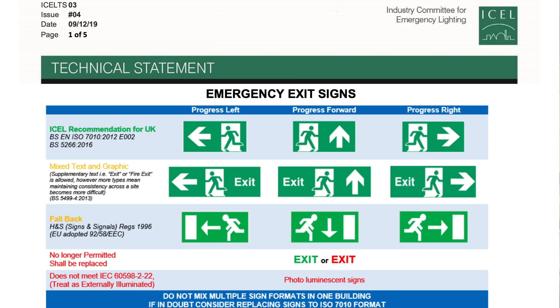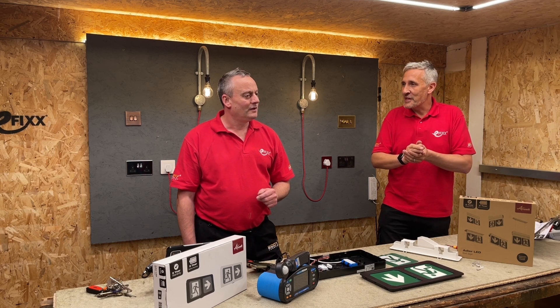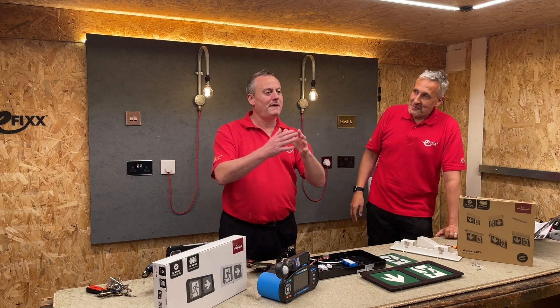There was a previous version of the EU signage directive — which was the era when we started getting rid of the word 'exit' on signage and moved to pictograms. Under that previous guidance there was a slightly different colour of green, and the arrow direction wasn't defined. So when Gary was in Gregg's the Bakers and the arrow was pointing downwards, under that directive it was probably right.